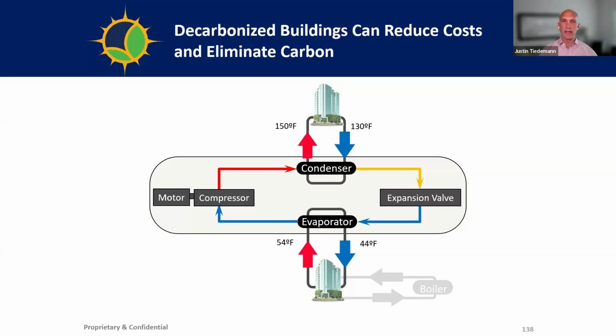Typical designs out there use 180-degree water, and heat pump technology right now can only meet that 140 to 150 degree temperature. So it's important to do the work to be able to use the technology and have as many technology options available as possible.